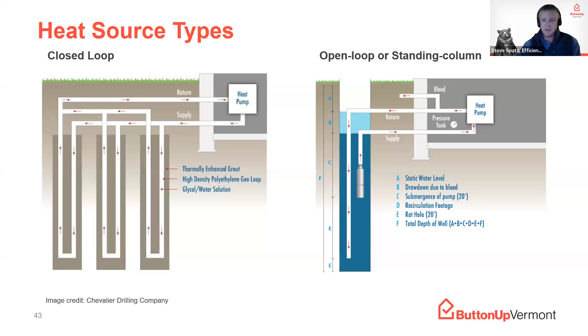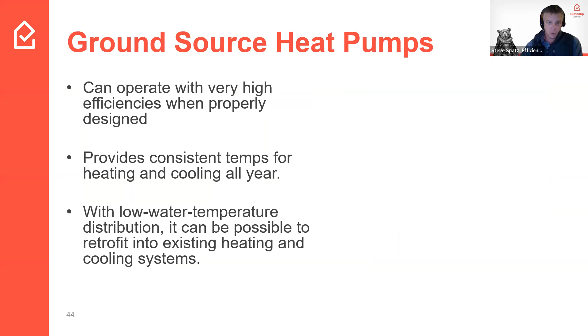You can get really good consistent COPs, efficiency throughout the year, and really good BTU output throughout the year. Again, this is a low temperature water distribution type that we're talking about, similar to the air to water. These ground source loops can be connected to existing systems, or they can be built as new. It is pretty common for ground source systems for an existing building to be integrated into a forced air system. That's a pretty common application where you're actually putting a ground source refrigerant coil into an existing forced air furnace, and then that is being used for the primary or secondary heating for the house.